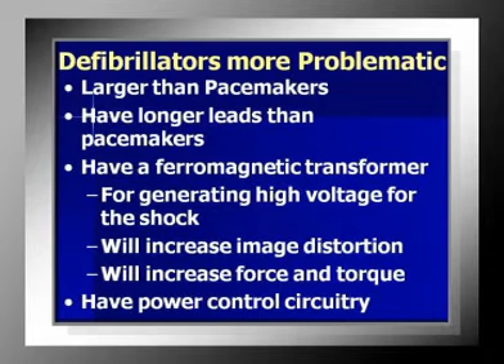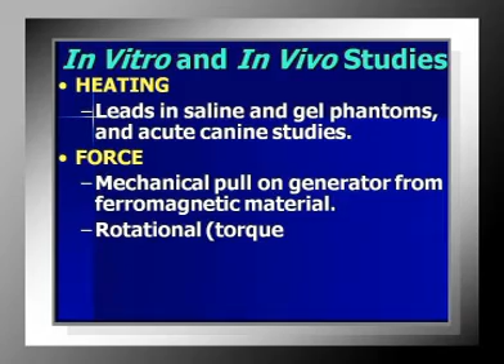So defibrillators are more problematic because they're larger than pacemakers, they have longer leads than pacemakers, and they have a ferromagnetic transformer, which is used for generating the high voltage for the shock. This could increase image distortion, and maybe there will be forces or torques acting on the generator that may be dangerous. And they also have power control circuitry, which has ferromagnetic materials in it. So Ariel did this very nice study, in vitro and in vivo, where we looked at heating, force, function, and then image distortion.